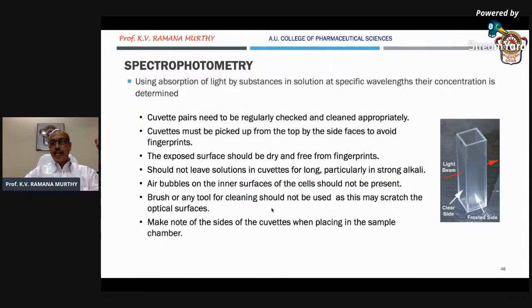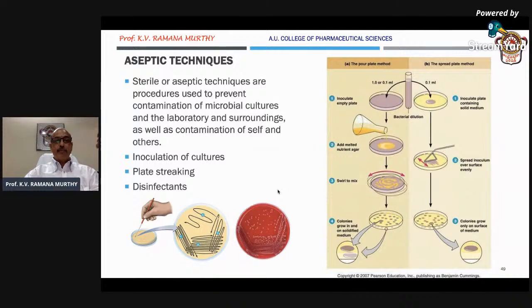The least we can talk about is handling cuvettes used for UV spectrophotometry, both visible and UV regions. Many times students hold the cuvettes on the transparent side instead of the opaque side, and nobody bothers to check if there are air bubbles or particulate matter in the sample. All this must be taught properly - what level of liquid should be kept in the light path. Sometimes it's only half filled, but they still get an absorbance reading. You can get a reading on the machine regardless, but people should be taught properly how to clean and preserve the cuvettes. This must be explained to students thoroughly before they use the equipment.